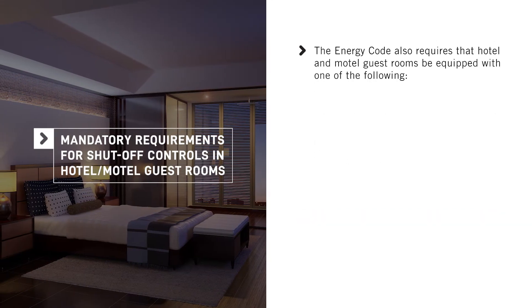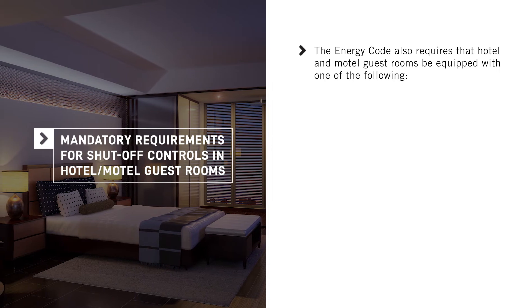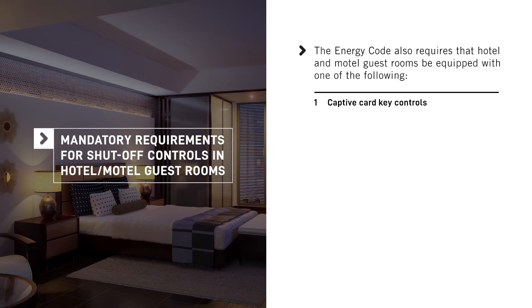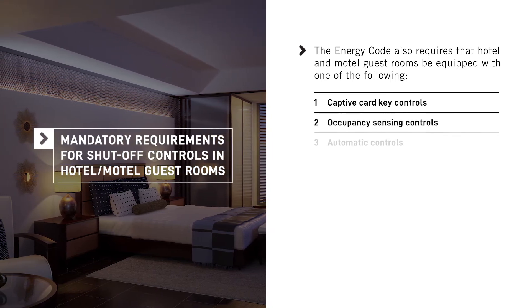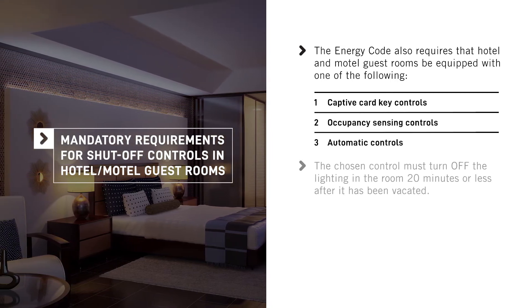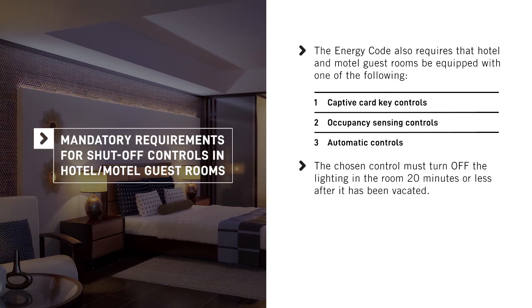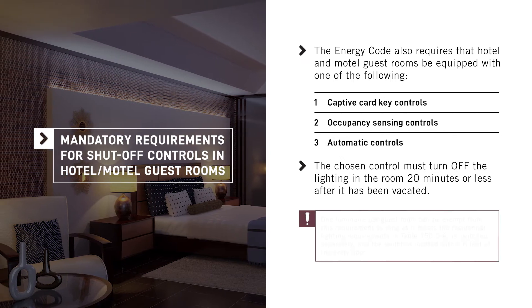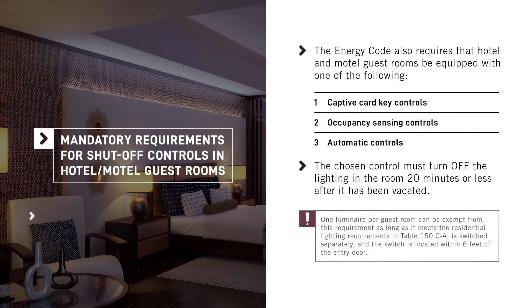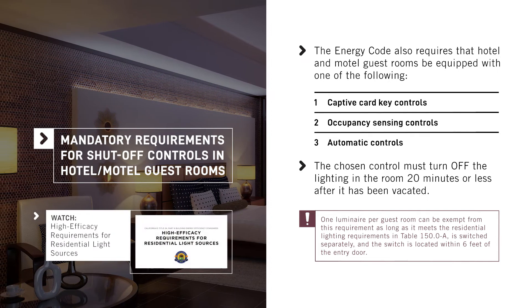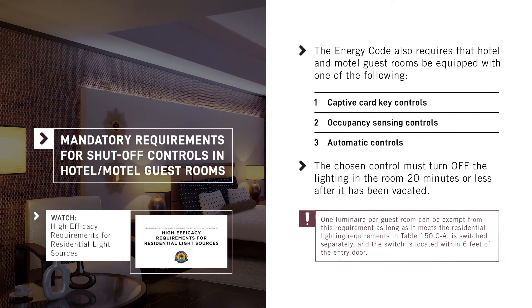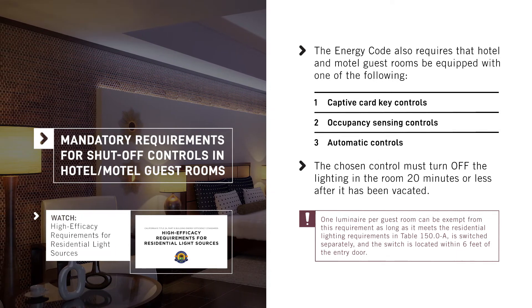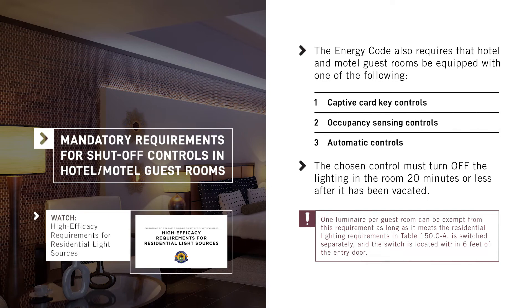The Energy Code also requires that hotel and motel guest rooms be equipped with one of the following: captive card key controls, occupancy sensing controls, or automatic controls. The chosen control must turn off the lighting in the room 20 minutes or less after it has been vacated. However, one luminaire per guest room can be exempt from this requirement, as long as it meets the residential lighting requirements in Table 150.0-A, is switched separately, and the switch is located within 6 feet of the entry door.